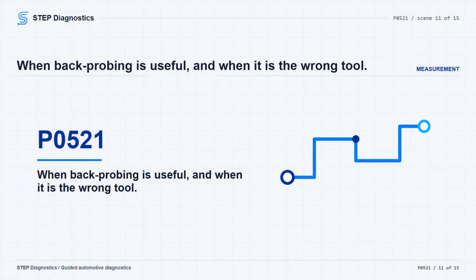Back probing has its place, but it is risky because the probe contact may be uncertain and the terminal can be damaged. Use it only when the circuit has to be tested under real operating conditions, when voltage drop has to be measured, or when opening the circuit could change module behavior. In voltage drop testing, expect a small amount of voltage, less than 5% of circuit operating voltage. A 0-volt result means the test setup is wrong. The circuit is not flowing current, or the back probe connection is bad.